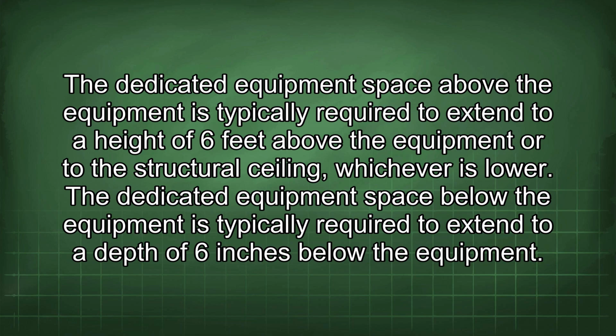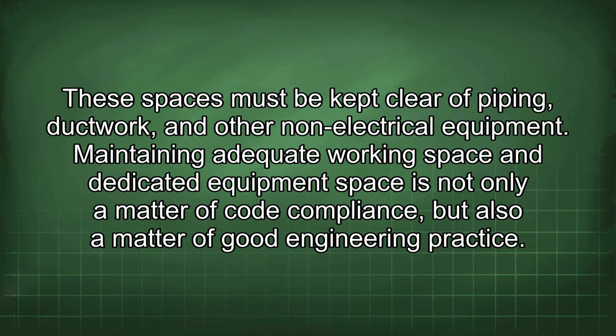The dedicated equipment space above the equipment is typically required to extend to a height of 6 feet above the equipment or to the structural ceiling, whichever is lower. The dedicated equipment space below the equipment is typically required to extend to a depth of 6 inches below the equipment. These spaces must be kept clear of piping, ductwork, and other non-electrical equipment.